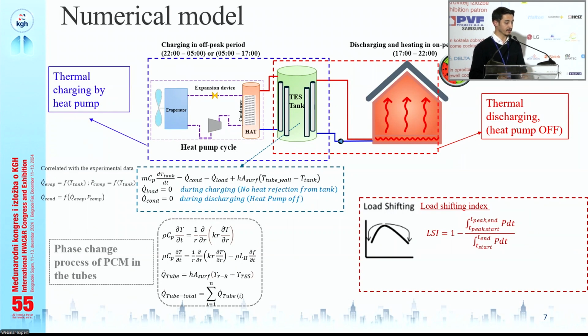And in this case, the load is 0 during charging, and the condenser load is 0 during discharging, representing the operational modes, actually. And then once the internal energy of the water inside the thermal energy storage tank changes, this allows the water to exchange heat with the PCM inside the tubes.